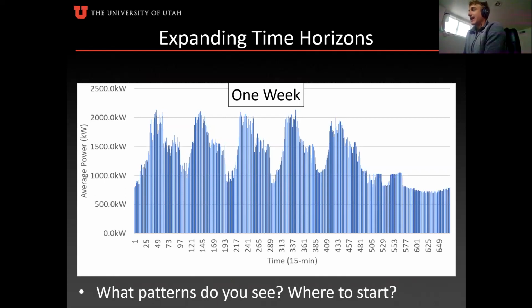What I'm noticing here in this pattern is that it looks like on their weekdays, they're very front loaded. So they get to work, they start something in the morning, and then, assuming that's maybe 8 a.m., it looks like their major power draw is somewhere between maybe 8 a.m. and 12 p.m. And then in the afternoon, they must have something shut off because their afternoon is much lower than their morning on a work day. Awesome. That's a really detailed observation, Michael.